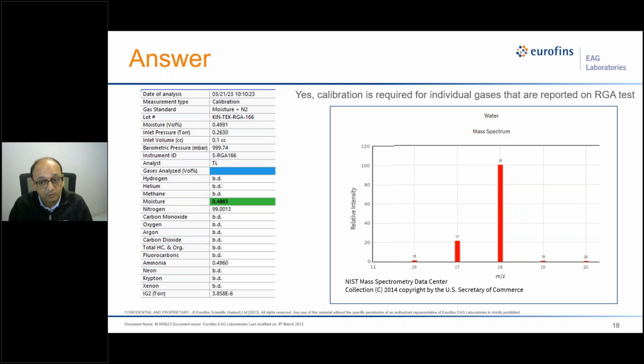Now, this is just one example, but there are several other gases that we have to figure out. And there is a complex method of deconvoluting these masses and their numbers. That's why calibration is probably the most critical part of RGA analysis. So the answer is yes, we have to calibrate for each gas, and we also have to look for the fragments which could interfere with our assessment of the number for that mass. So we have to correct for that too. The calibration needs to be done for that gas as well as other gases, to confidently conclude that my final numbers are free of any interferences, and based on the calibration data we can calculate this.